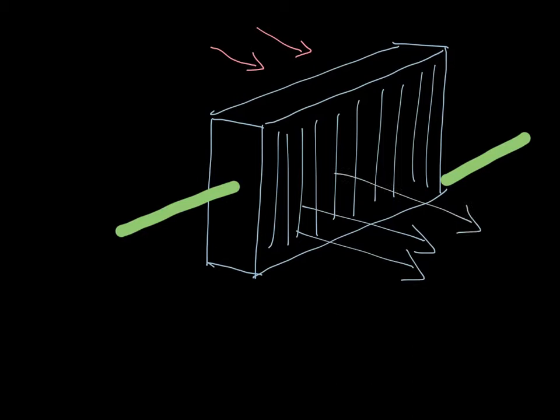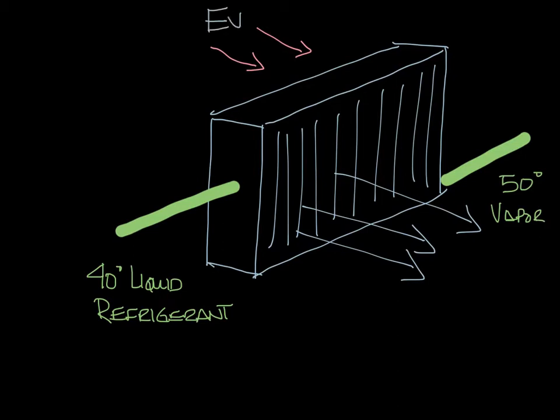This transfer of heat from the air to the refrigerant lowers the temperature of the air so that it can be delivered to the occupied space for cooling. It also causes the refrigerant to evaporate. You have 40 degree liquid refrigerant going into your evaporator and after the air passes through and the heat transfer happens, it comes out as a 50 degree vapor. So this is your evaporator.